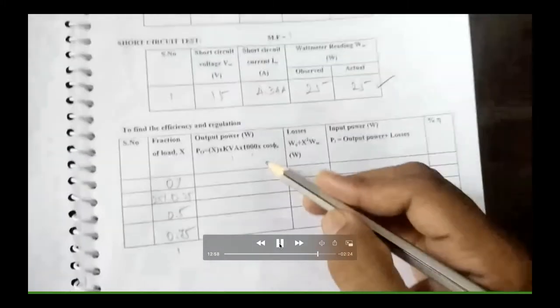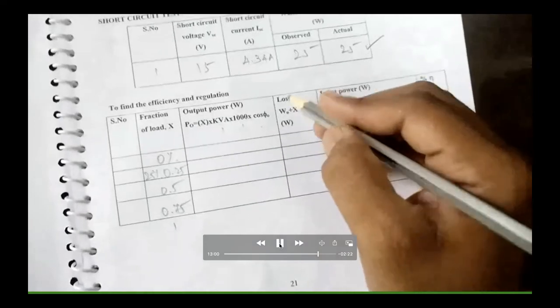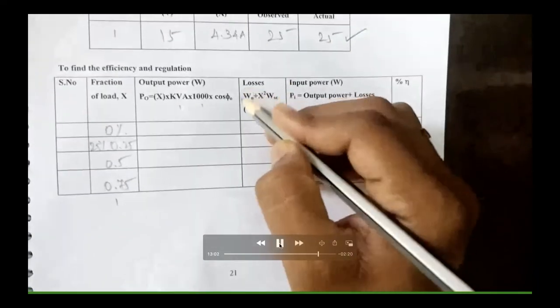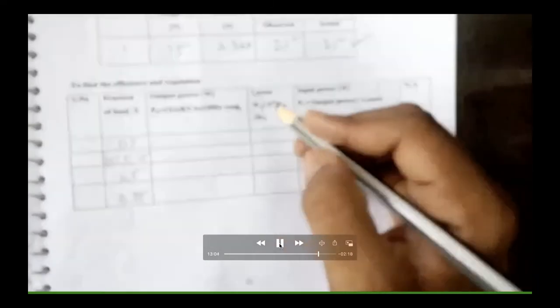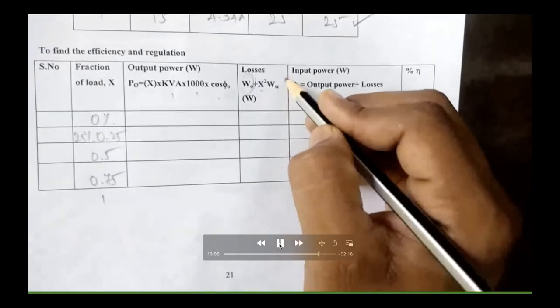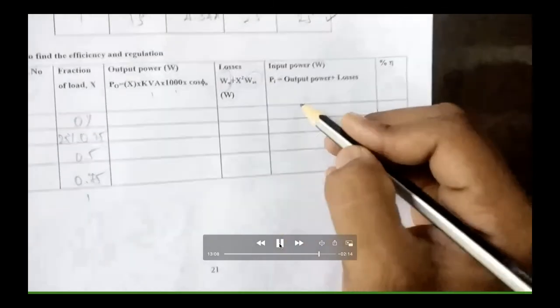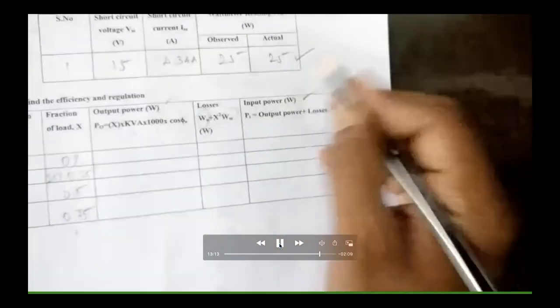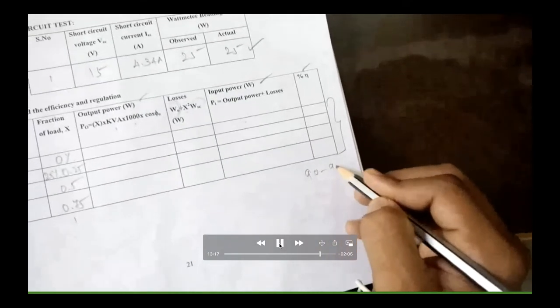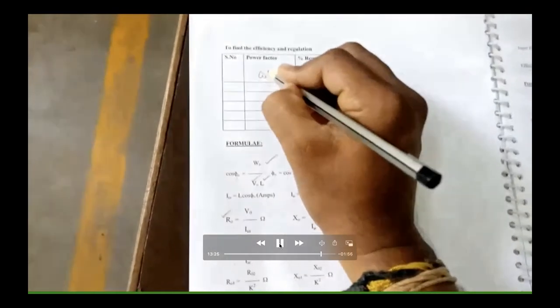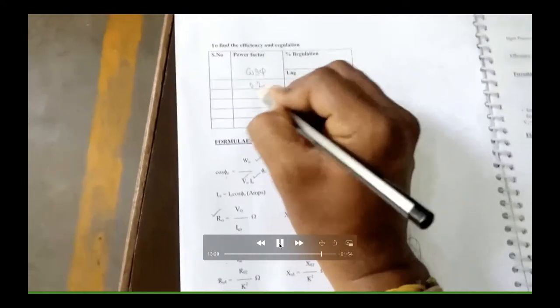So after finding that, you can calculate the output power one by one. Then you can calculate the losses as open circuit W naught plus x square into WSC. So you know x, the fraction of load. We know W naught. We know x square. We can calculate the losses, the input power, which is output power plus losses. Efficiency will be output by input. So it will be almost 97 percent to 98 percent. So after all those things, you can find out the efficiency as well as the regulation of the transformer.